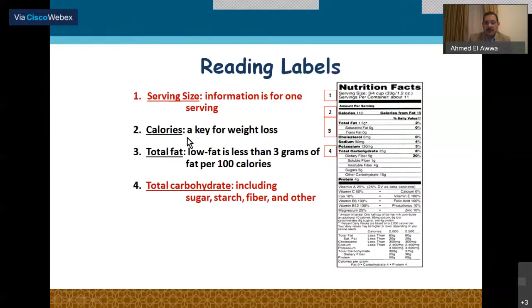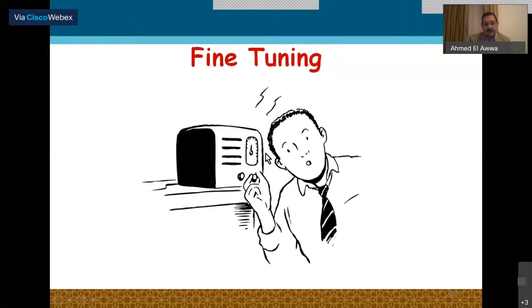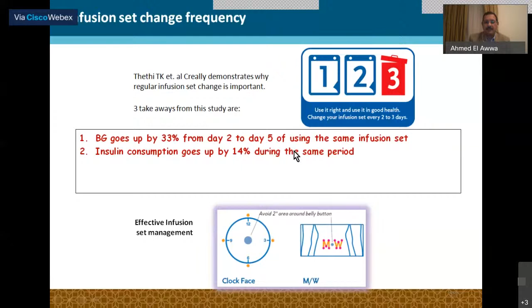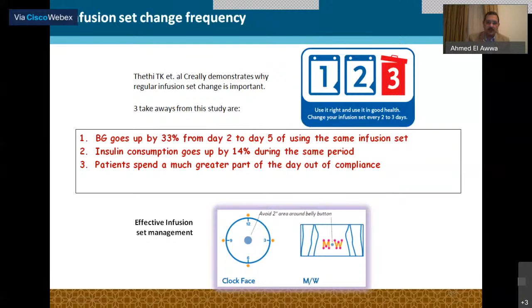After setting up the basal and bolus, insulin carbohydrate ratio, insulin sensitivity factor, and the many calculations used to do that, then you do the fine tuning and adjust the doses to get the readings you are aiming at. It's very important for the pump to change the infusion set every 3 days on average, sometimes less, sometimes more, sometimes 3.5 days. But most studies said after the 3rd day, there is a risk of partial occlusions and an increase in insulin consumption by 33%.